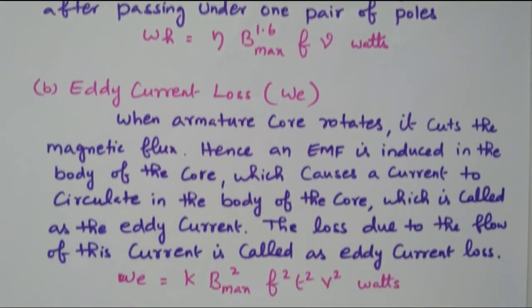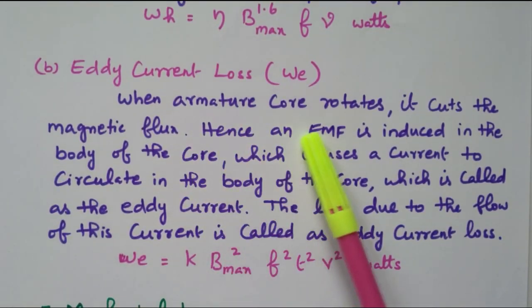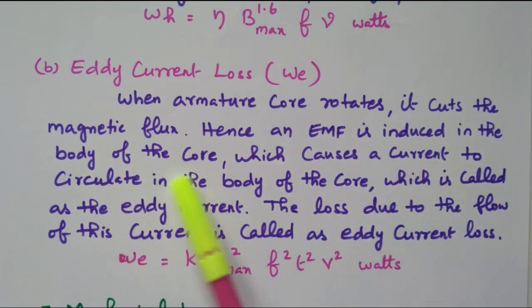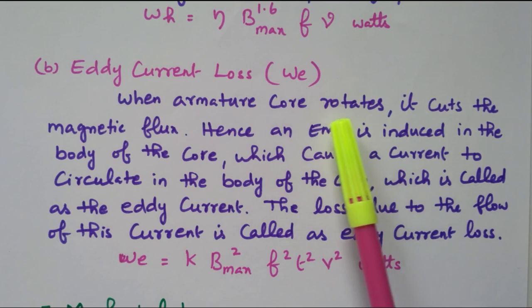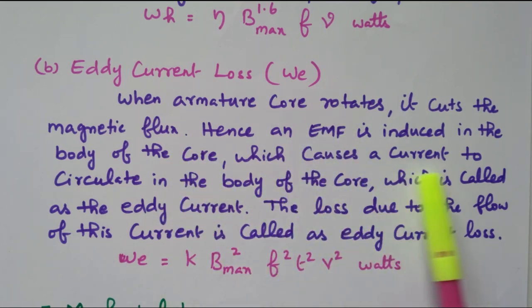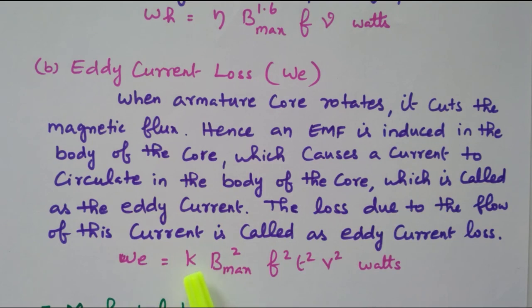Then we will see the eddy current loss. When the armature core rotates, it cuts the magnetic flux. Hence EMF is induced in the body of the core. The armature, while rotating, cuts the flux. The core also cuts the magnetic flux. So due to that, EMF is generated, which causes a current to circulate in the body of the core. That current is called eddy current. Due to that eddy current, some losses will happen. These two losses — hysteresis and eddy current — are due to the iron core.